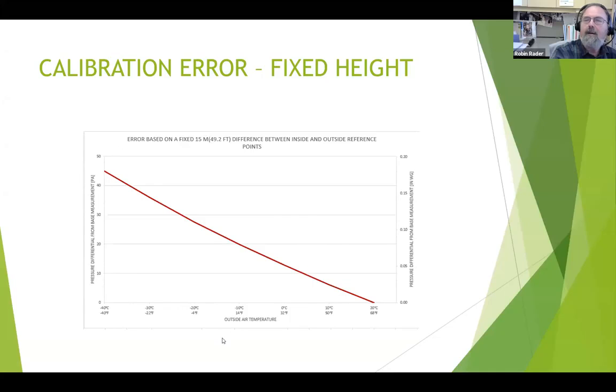This is a graph of the offset due to height difference. Reading this, you can see that you can get up to about 2/10 of an inch difference if you set the zero of your building static pressure sensor at 68 degrees and it went down to 40 below. So that's the amount of offset that would happen if you had an approximately 50-foot difference in the elevation of your sensing tubes.